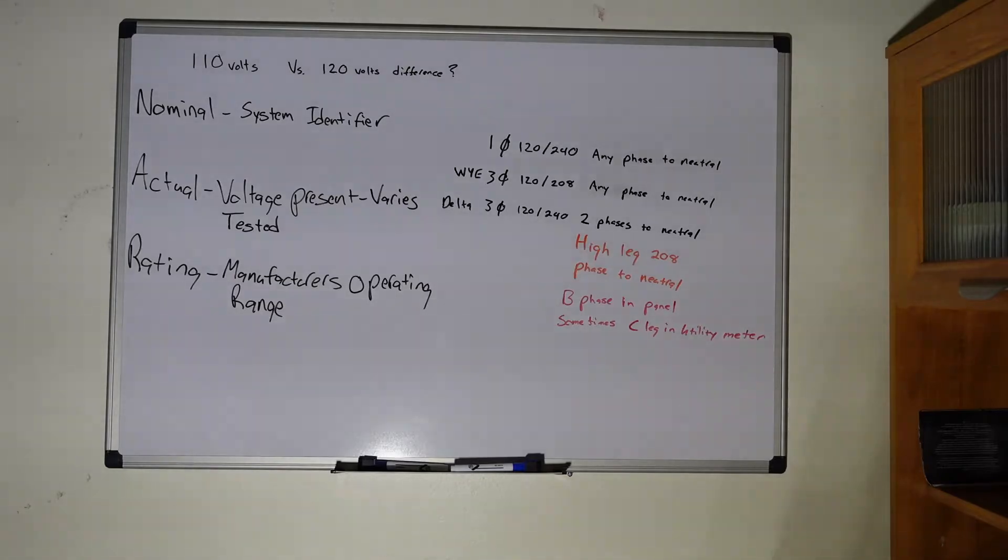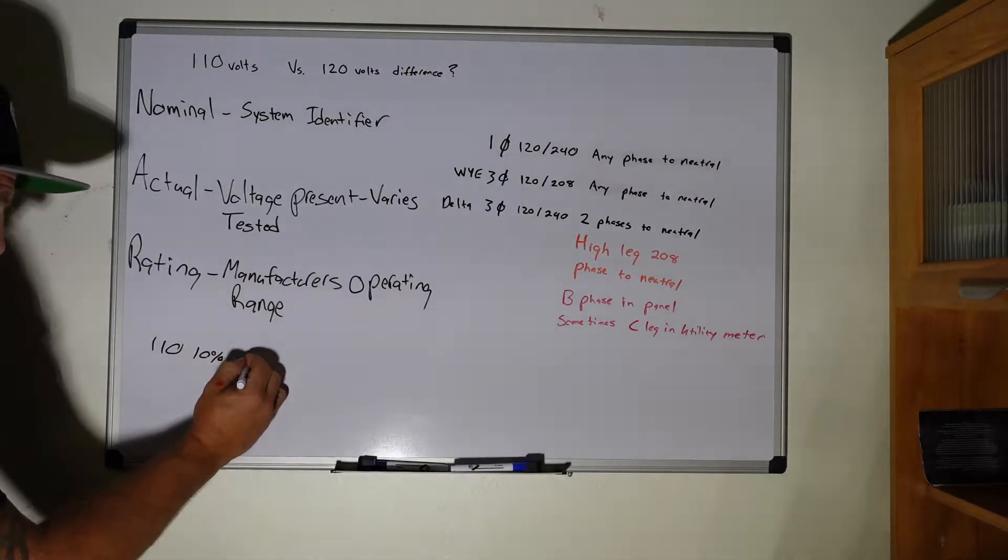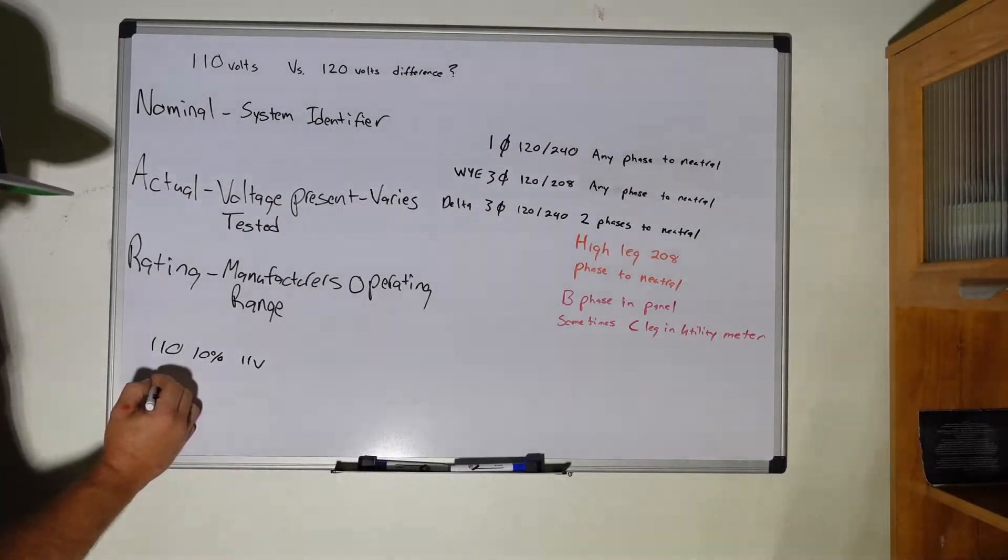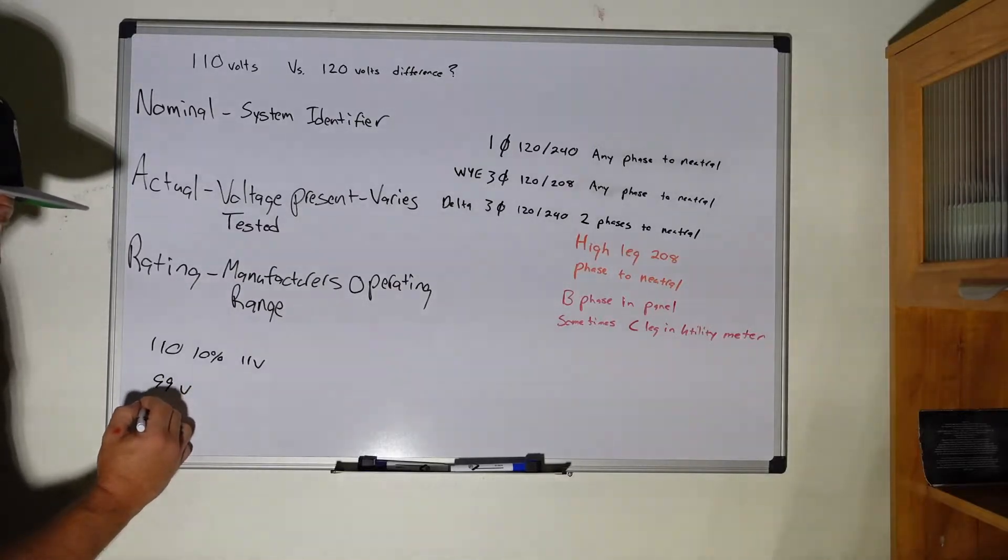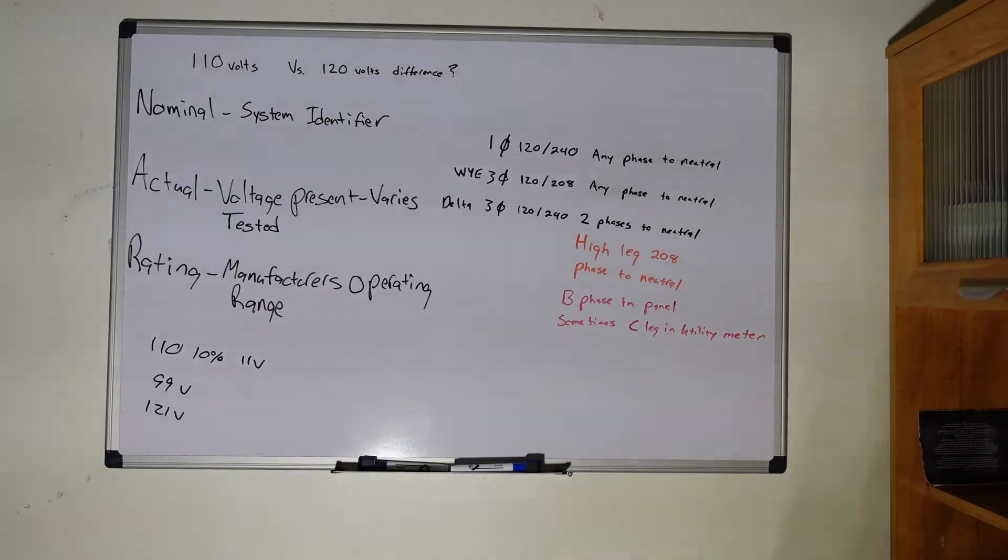So on 110, 10% of that is 11 volts, so you could get it down to basically 99 volts or as high as 121 volts. The low side is kind of bad, the high side is 121 which would still operate, but that's all that's going to change just as your actual voltage changes.